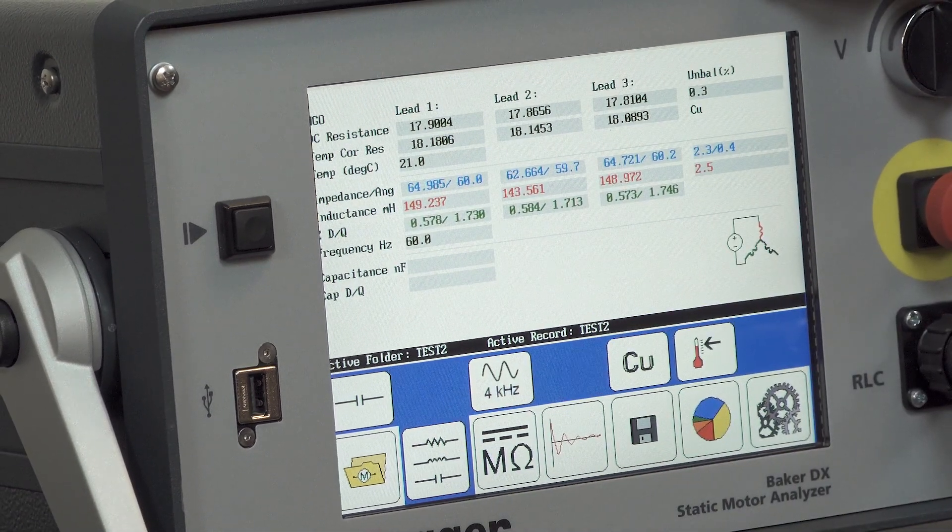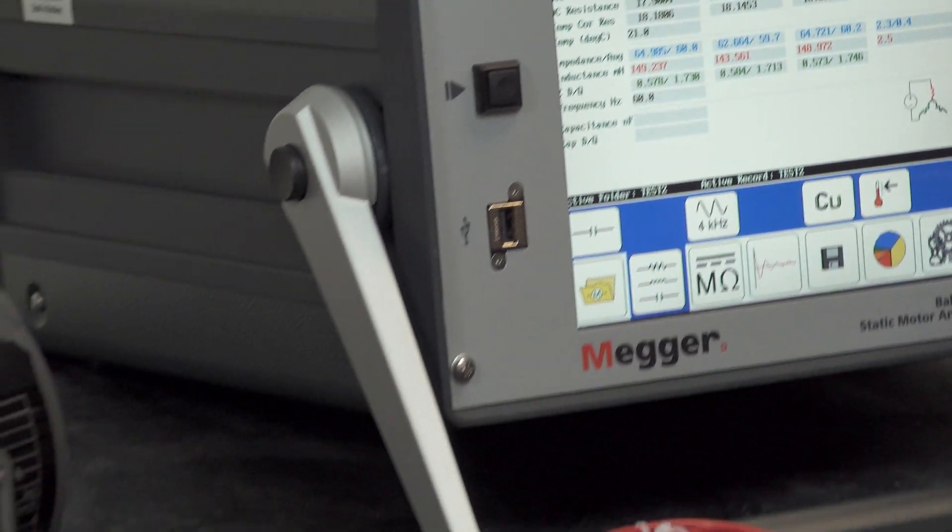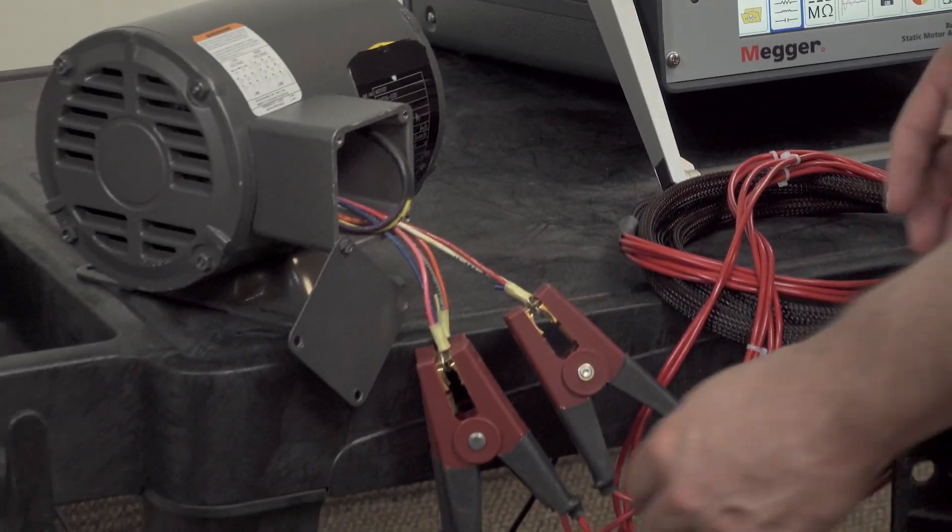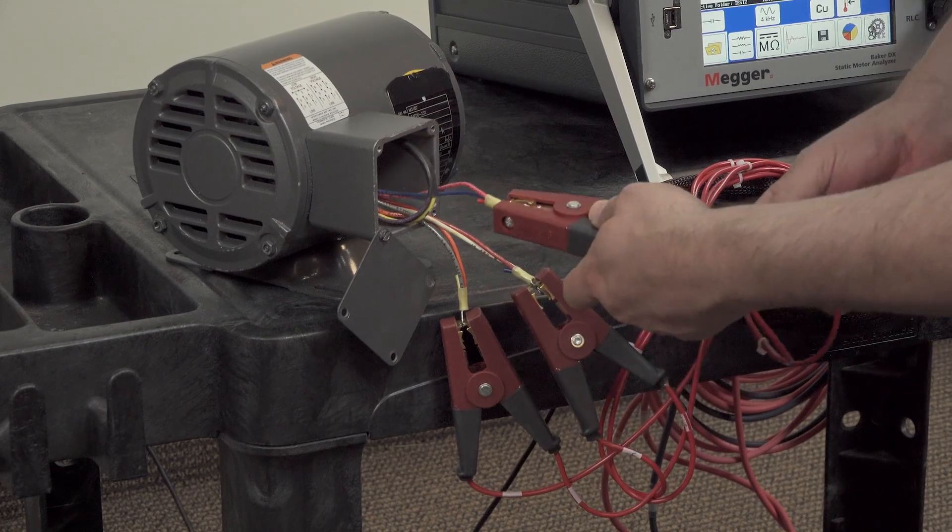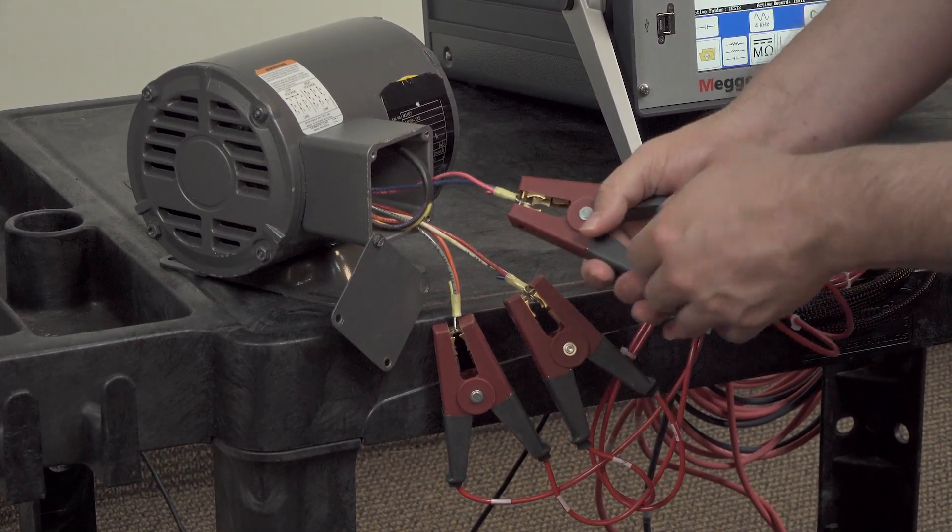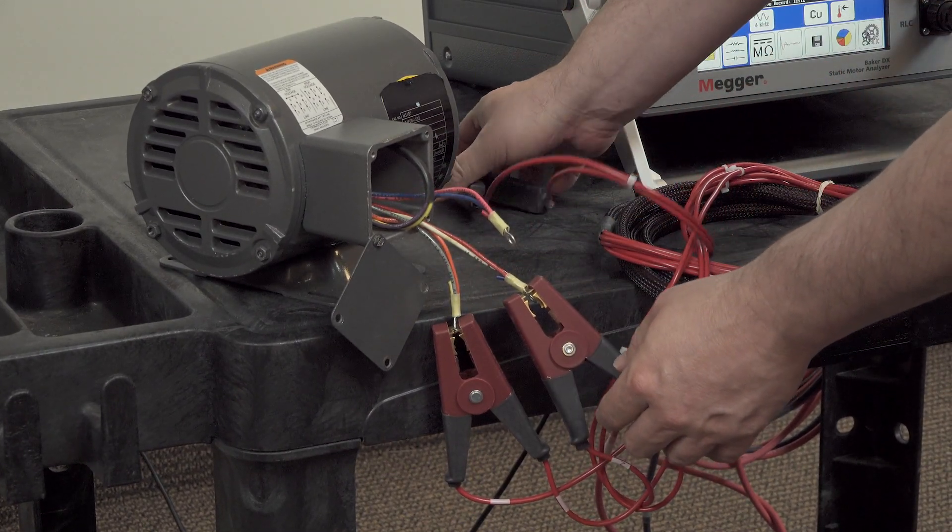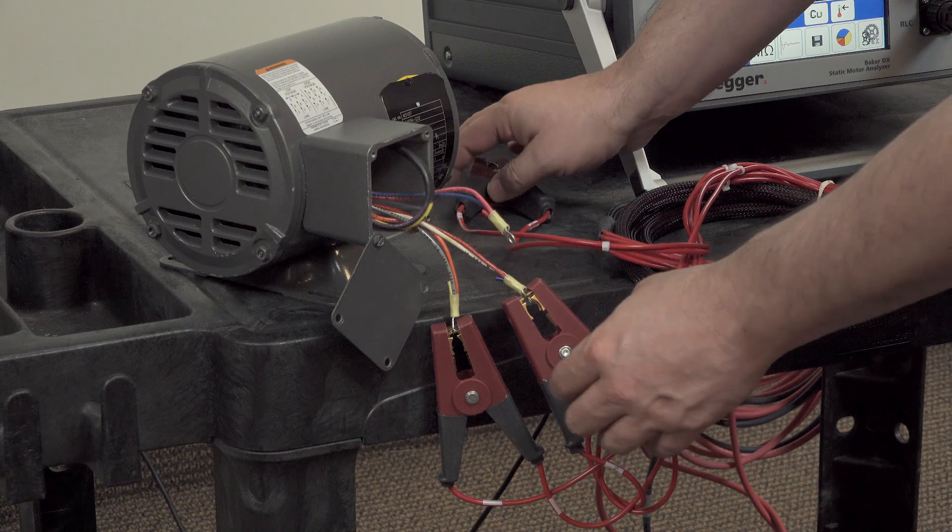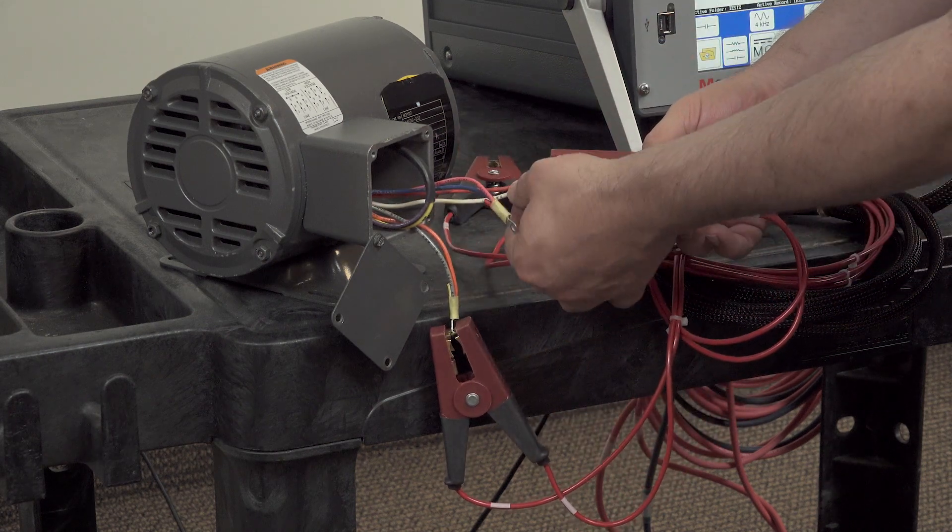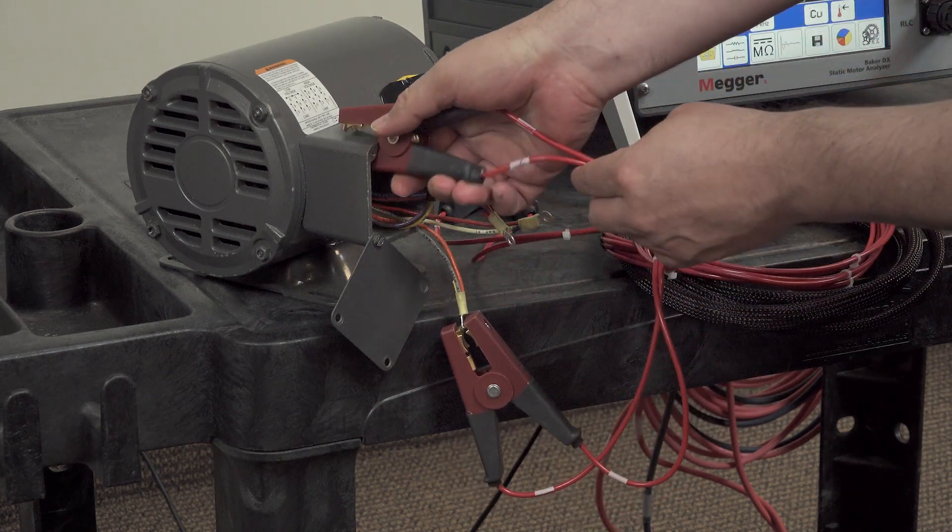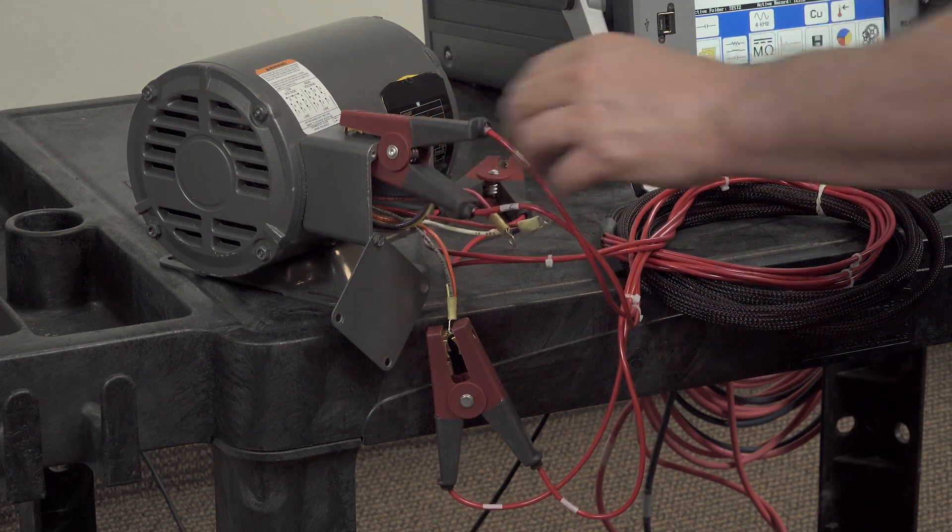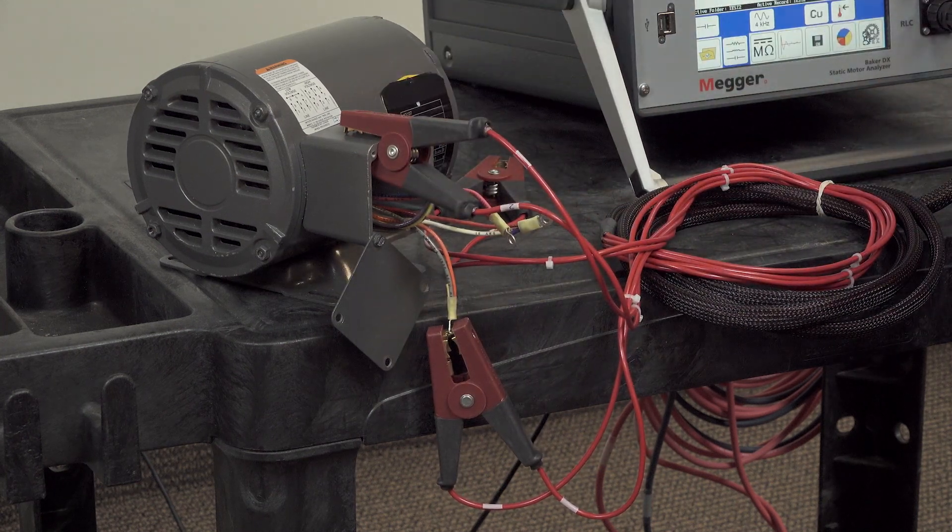But we have to change the lead configuration for this test. So what we want to do is remove lead 3 and place it aside. And then take lead 2 and connect it to the ground, the frame in this case of the motor.